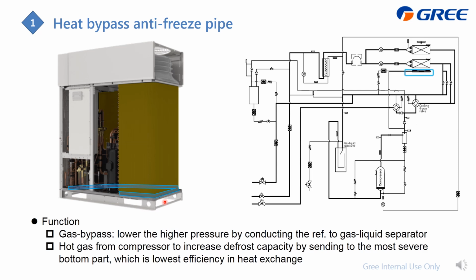So we just sacrifice the bottom part and make it connect with the compressor. During the defrost, when we send the hot gas from the compressor to the outdoor heat exchanger to melt the ice, and the ice becomes water, we also send a partial flow from the compressor discharge to the bottom side, which is here, and it is controlled by this gas bypass valve. So we can prevent the water from becoming ice at the bottom, right? And this way we can raise the defrosting efficiency, which means we can raise the heating performance.